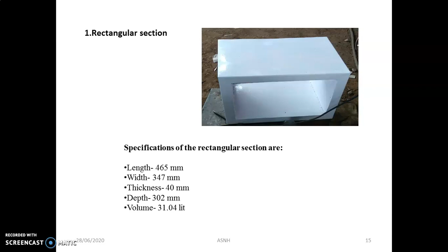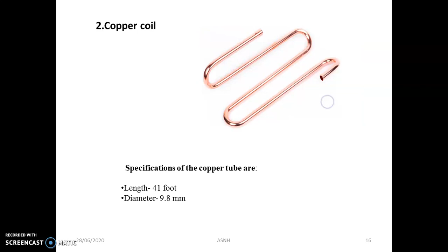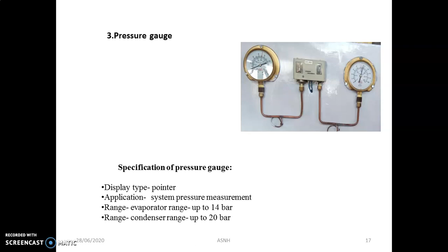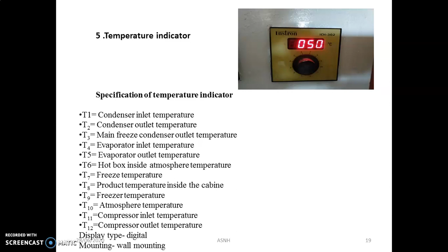So here you will get an idea about the rectangular box which is kept over the refrigerator. These are some of the dimensions designed. Copper tubes, pressure gauges. If you want to find out the COP of the refrigeration system, we must know the condenser inlet, condenser outlet, and simultaneously the evaporator outlet or evaporator inlet. So that's why the pressure gauges are essential. Voltmeter and ammeter are also needed in order to know the performance. Temperature indicator is important while calculating the COP. Energy meter is used to count the blinks in order to find the power consumed. LPHP cutoff is there. On-off controller is there.